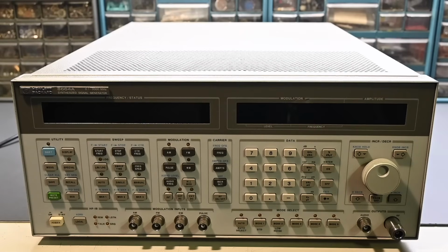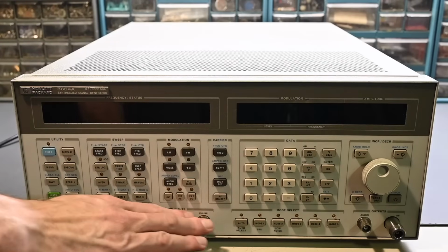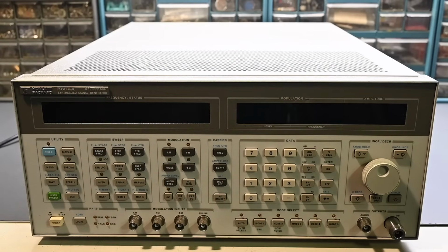In addition to the main RF output, this has a low frequency output on this BNC connector. It goes from 0.1 hertz to 400 kilohertz, and it has the same accuracy as the time base. This signal generator has 2 internal modulation sources plus the external modulation inputs. Because it has multiple modulation sources, it can create a subcarrier waveform. It also has a variety of sweep functions that are built in.